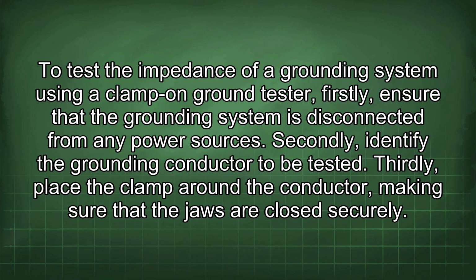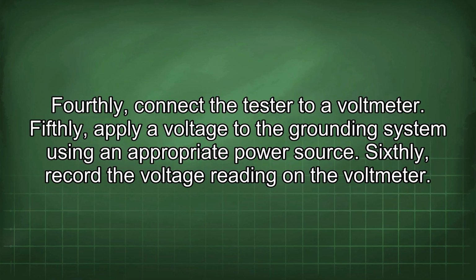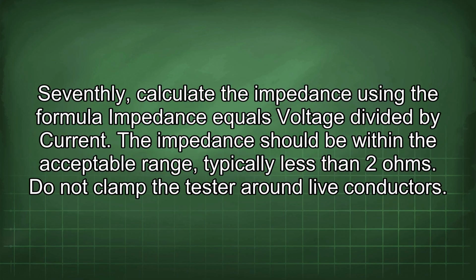To test the impedance of a grounding system using a clamp-on ground tester, firstly, ensure that the grounding system is disconnected from any power sources. Secondly, identify the grounding conductor to be tested. Thirdly, place the clamp around the conductor, making sure that the jaws are closed securely. Fourthly, connect the tester to a voltmeter. Fifthly, apply a voltage to the grounding system using an appropriate power source. Sixthly, record the voltage reading on the voltmeter. Seventhly, calculate the impedance using the formula impedance equals voltage divided by current.